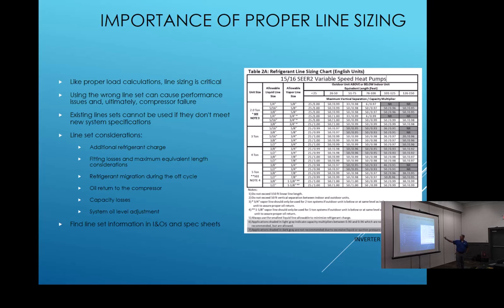So still read your installation instructions, but if it's already in the existing home, fine. Now if it's in the existing home and it's 150 feet away in a commercial setting, you might want to look at it, because then depending on whether the unit's above or below the air handler, you may have to have P-traps in it every so far.